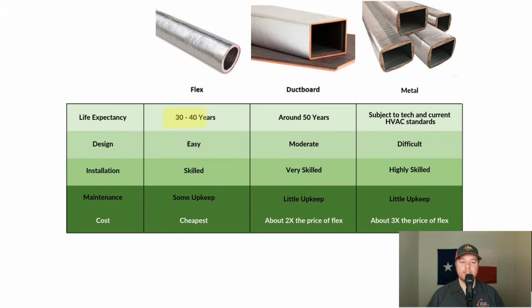So what's my overall summary and conclusion on these 3 ductwork types? So when it comes to life expectancy, we can see that flex ductwork can last upwards to 30 to 40 years. Ductboard, you might be able to push it as far as 50 years, and metal ductwork can pretty much last forever. However, with ductboard and metal, a lot of times it won't make it to its full life potential due to the new equipment, current HVAC standards, cleanliness, and sizing. So when it comes to ductwork designing, flex is fairly easy to design out, ductboard is moderately difficult, and metal is difficult to design out, because there's not a whole lot of wiggle room when it comes to the installation.